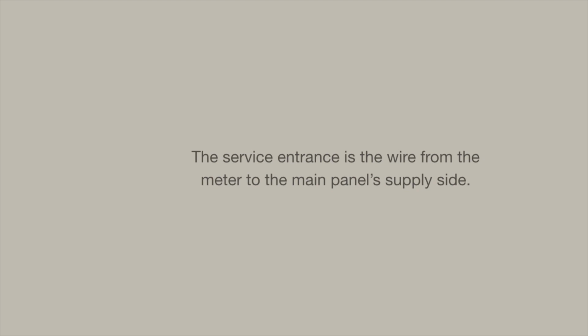Service entrance. The service entrance is the wire from the meter to the main panel's supply side. Sometimes this wire is not visible because the main panel is on the other side of the meter and no wire is visible at the point of entry. Once in the panel, the two main supply lines are connected to lugs which are attached to two separate bars, commonly known as bus bars, carrying power to the breakers or fuses.